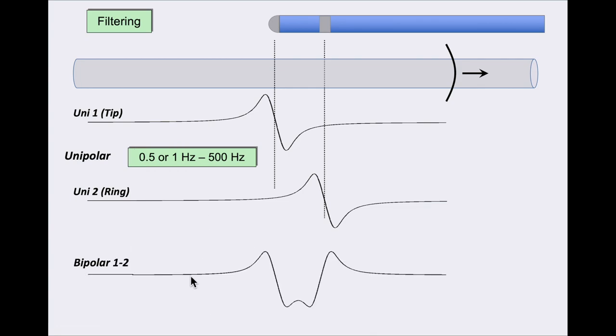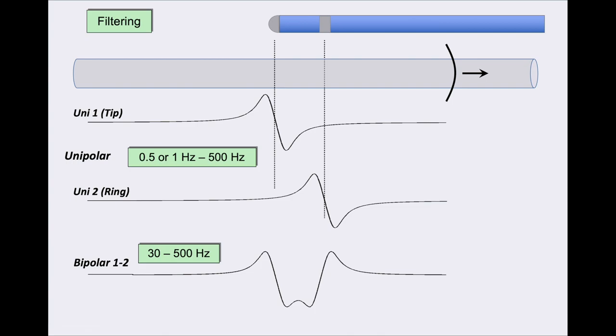For the bipolar electrogram, you do want to get rid of low-frequency signals because far-field signals are low-frequency signals. Even though using 30 hertz eliminates far-field signals, it may add additional components to the electrogram — but that is less critical because, as we will see further into this talk, we always use the unipolar electrograms to select our activation times. So typically for bipolar electrograms, we often use 30 to 500 hertz. We will continue with the bipolar electrogram in part two.